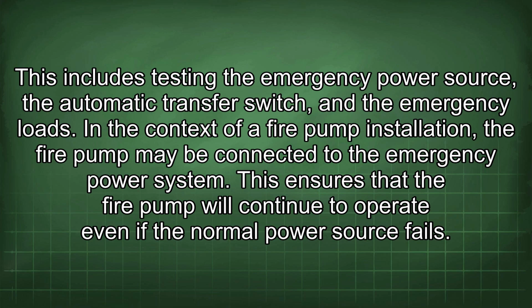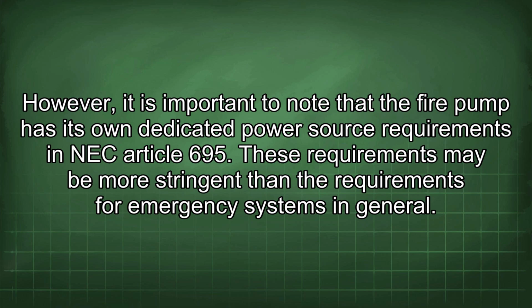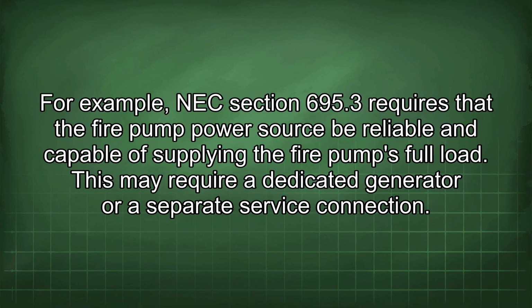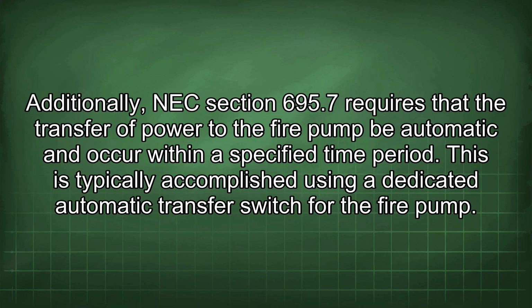In the context of a fire pump installation, the fire pump may be connected to the emergency power system. This ensures that the fire pump will continue to operate even if the normal power source fails. However, it is important to note that the fire pump has its own dedicated power source requirements in NEC Article 695. These requirements may be more stringent than the requirements for emergency systems in general. For example, NEC Section 695.3 requires that the fire pump power source be reliable and capable of supplying the fire pump's full load. This may require a dedicated generator or a separate service connection. Additionally, NEC Section 695.7 requires that the transfer of power to the fire pump be automatic and occur within a specified time period. This is typically accomplished using a dedicated automatic transfer switch for the fire pump.